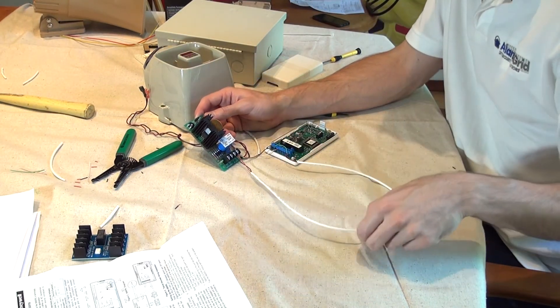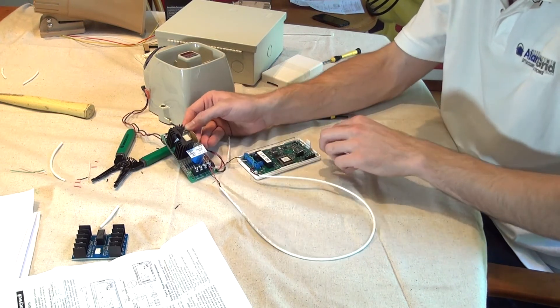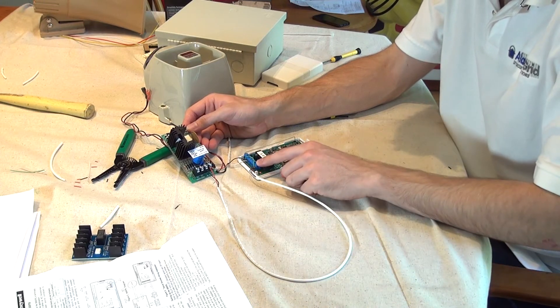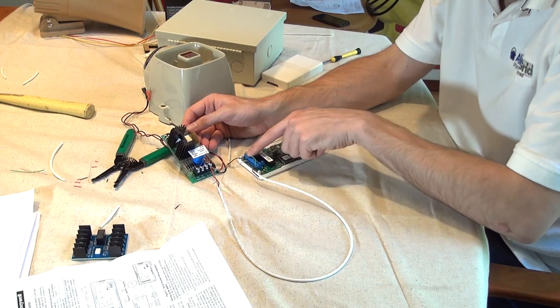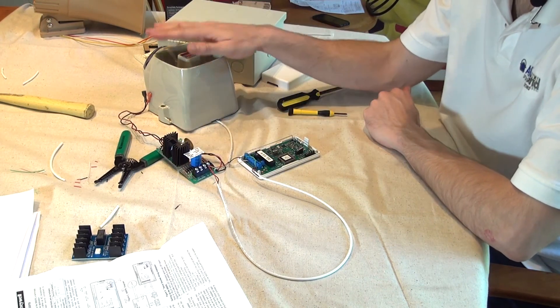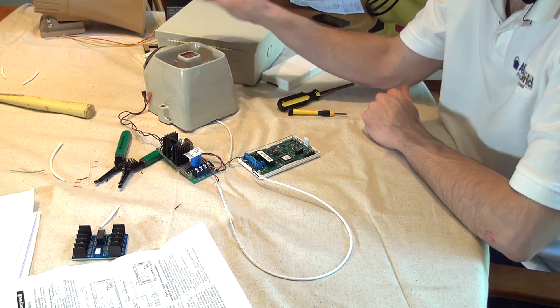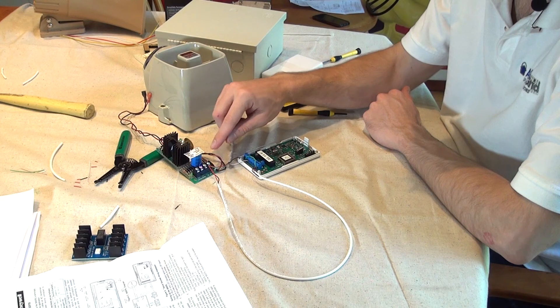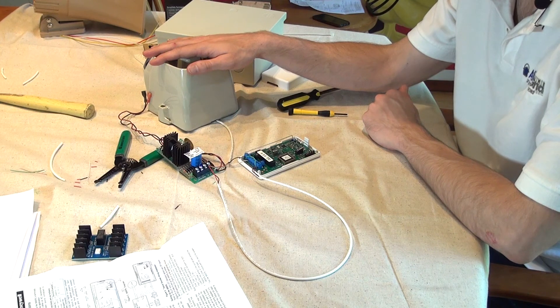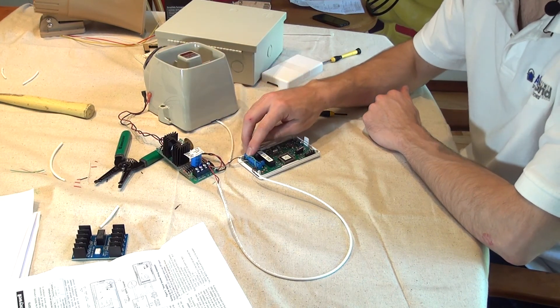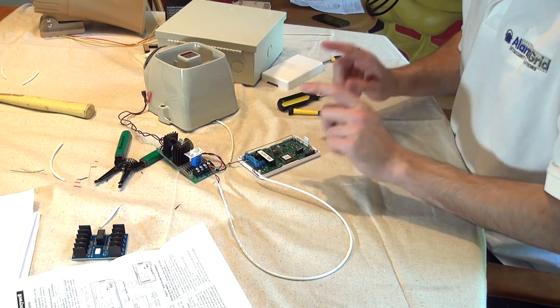Just to summarize the connections, we have our DC wiring from our power supply going to the bottom two terminals on our relay. We have a jumper wire from the bottom terminal to number two at the top. And then off our siren, we have our positive and negative for our siren and our strobe. The positives are going to DC output so that the auxiliary power supply is providing power to the siren. And we have our negatives going to our relay common so that the siren will know to kick on when the relay kicks on.